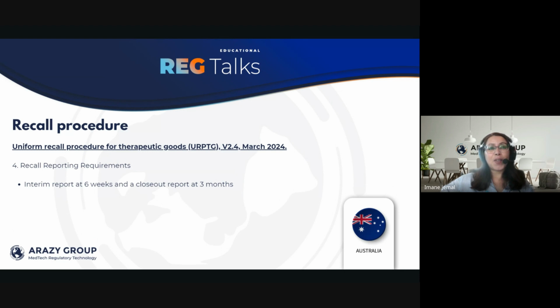The fourth update in the same guideline is about the refined recall reporting. Now the official report that is required from the manufacturer. So the reporting requirement, the TGA here was a little bit more flexible, giving a little bit more time to the manufacturer for the release of this official report regarding the recall. So they give a flexible time frame, typically including an interim report at 6 weeks and the closeout report at 3 months or any other agreed time. This depends on the communication, but generally 6 weeks and closeout report 3 months.